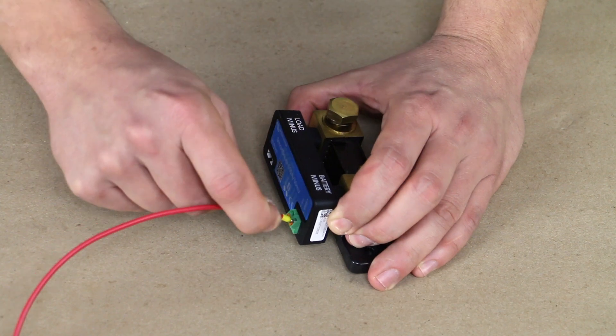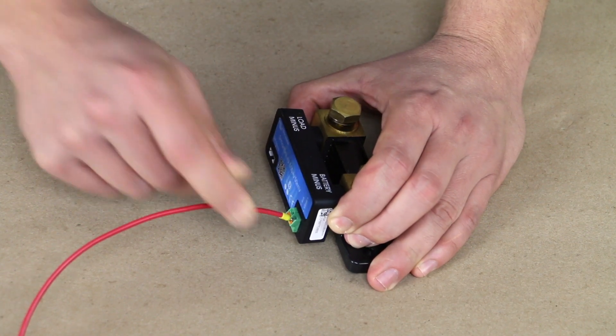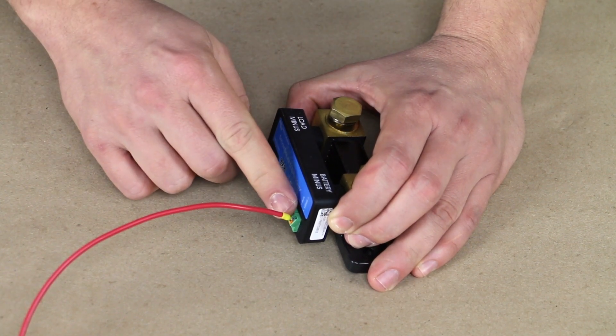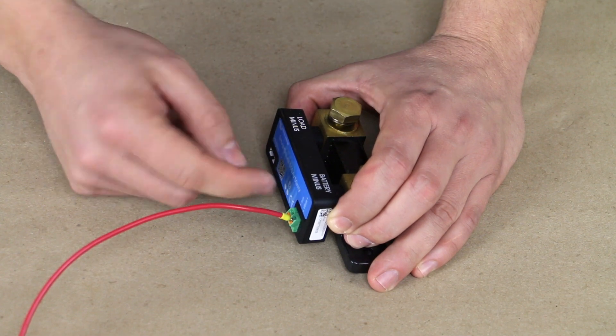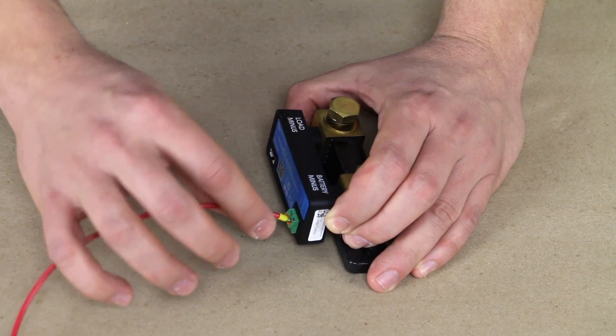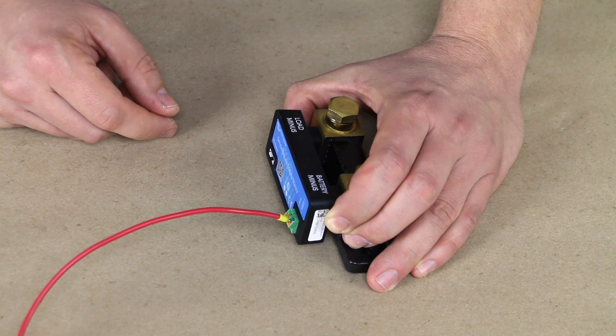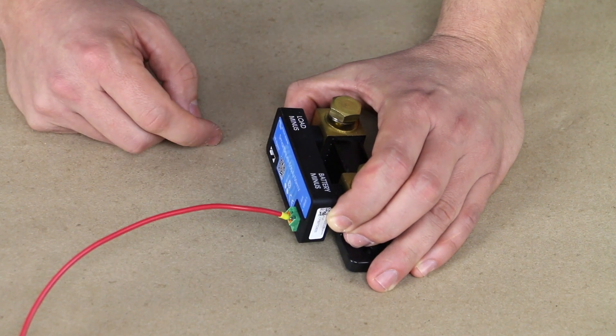And so this particular ferrule that I use works for this more shallow connection as well as some of the deeper inputs. And it makes sure that you're not going to be able to pull it out. If you use a ferrule that's too short, it's not going to get in there and grab, and it's more likely to pull out of that connection. So that's how you would add a ferrule.